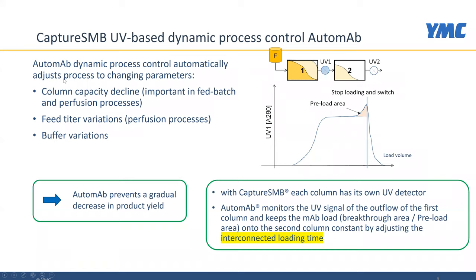AutoMab can account for column capacity decline, feed titer variations, and buffer variations, and it prevents a gradual decrease in product yield. It works by impacting the interconnected loading time—whenever the columns are loaded in series and the threshold is reached, the UV-based controller stops the interconnected loading without user interaction. This software algorithm influences process parameters, namely the interconnected loading time, and that needs to be considered in process validation.